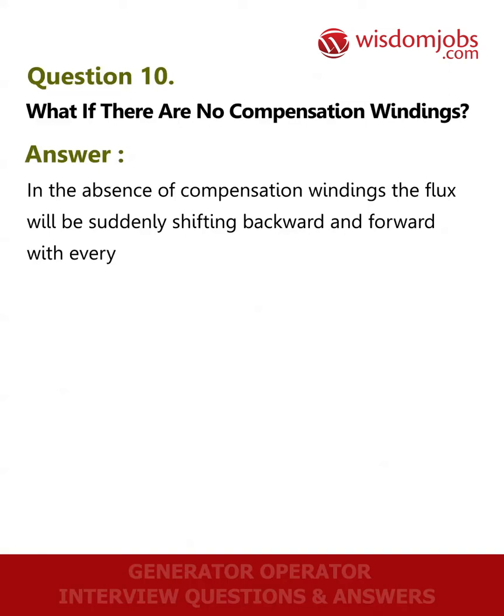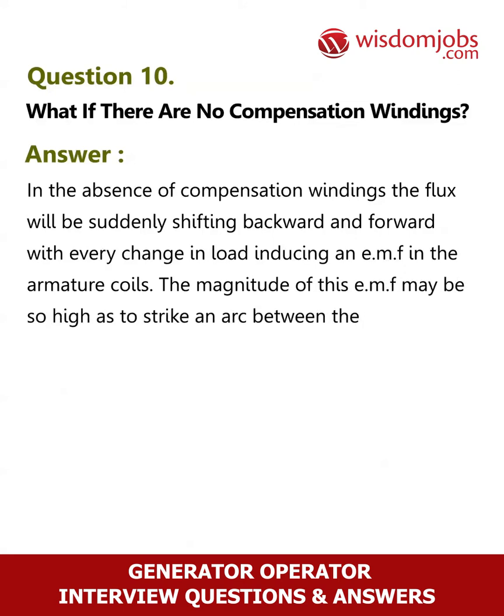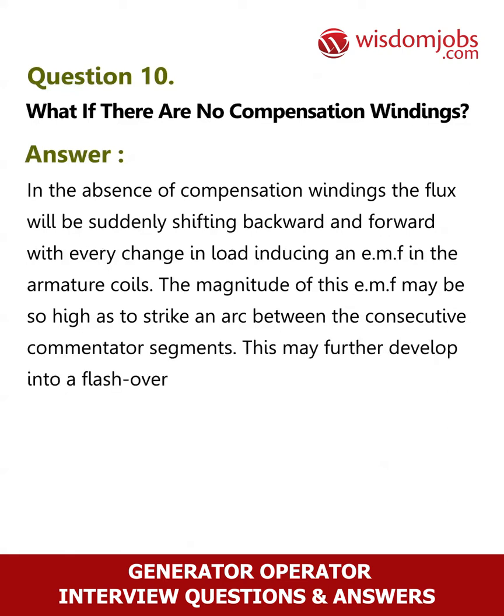Question 10: What happens if there are no compensation windings? Answer: In the absence of compensation windings, the flux will be suddenly shifting backward and forward with every change in load, inducing an EMF in the armature coils. The magnitude of this EMF may be so high as to strike an arc between the consecutive commutator segments, which may further develop into a flashover around the whole commutator, thereby short-circuiting the whole armature.